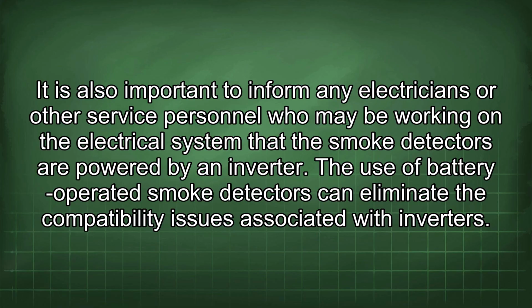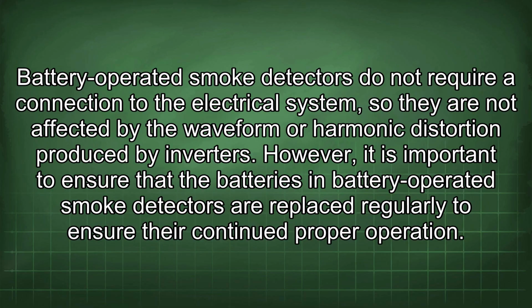The use of battery-operated smoke detectors can eliminate the compatibility issues associated with inverters. Battery-operated smoke detectors do not require a connection to the electrical system, so they are not affected by the waveform or harmonic distortion produced by inverters. However, it is important to ensure that the batteries in battery-operated smoke detectors are replaced regularly to ensure their continued proper operation.